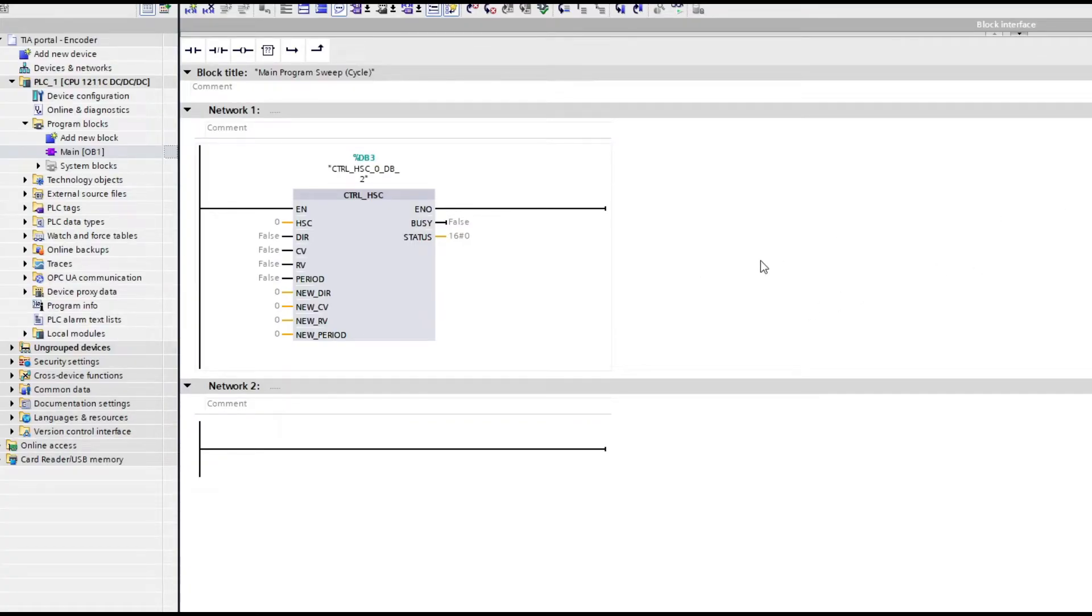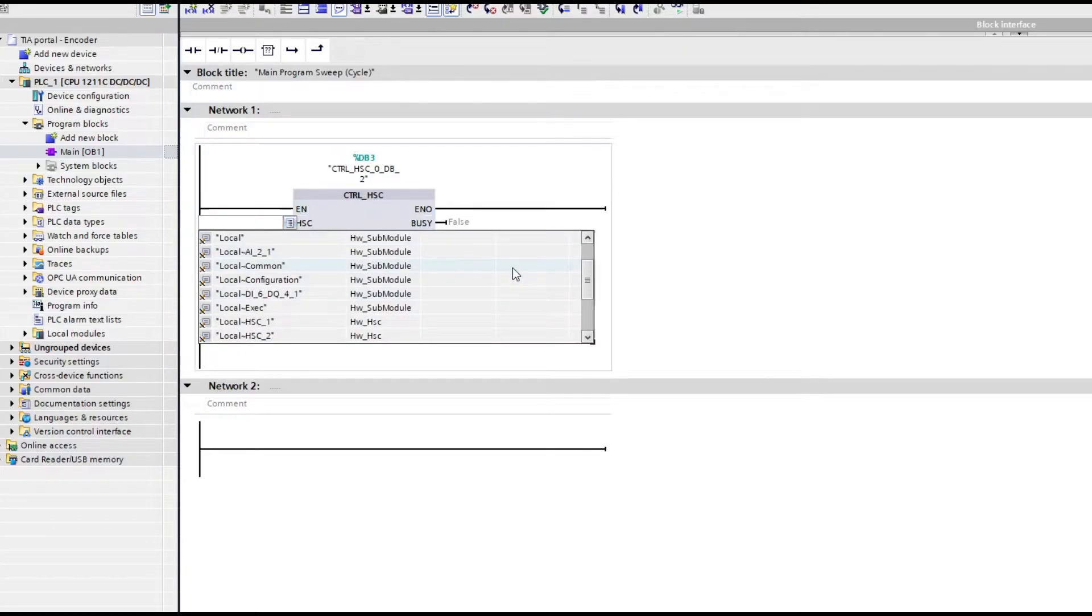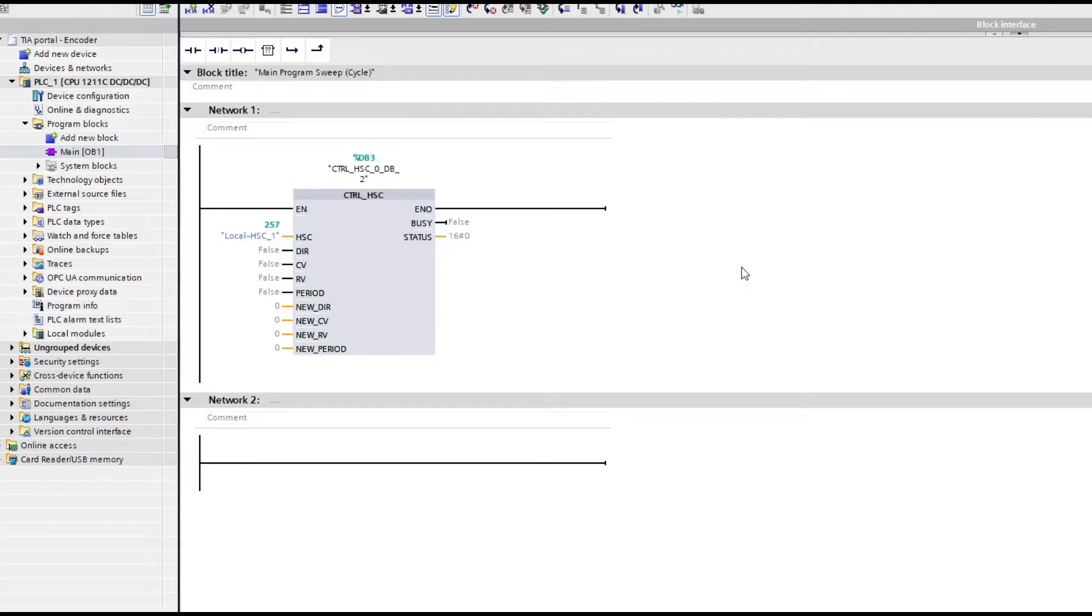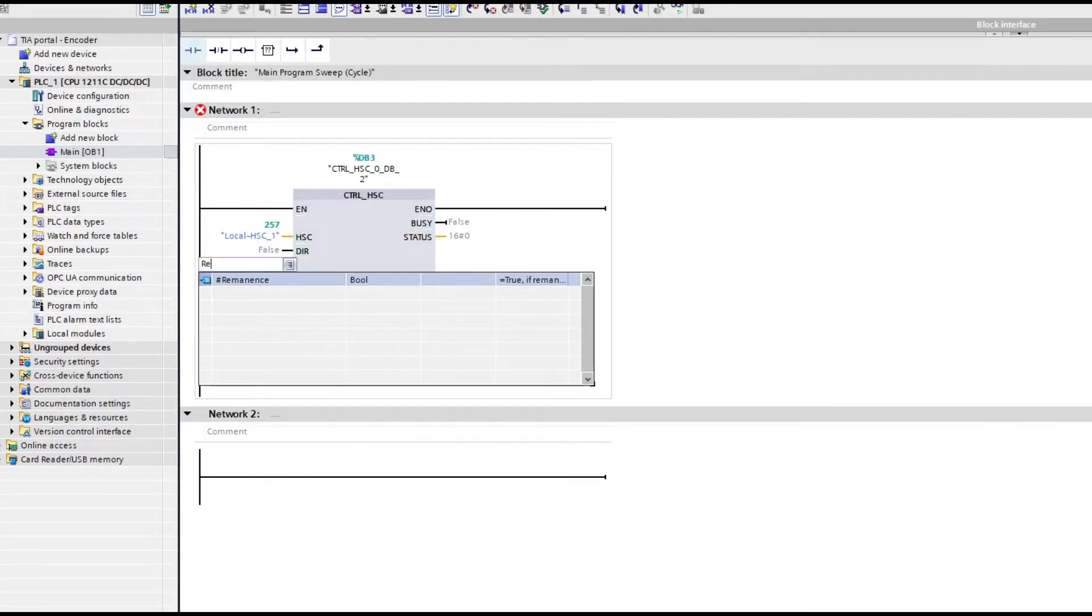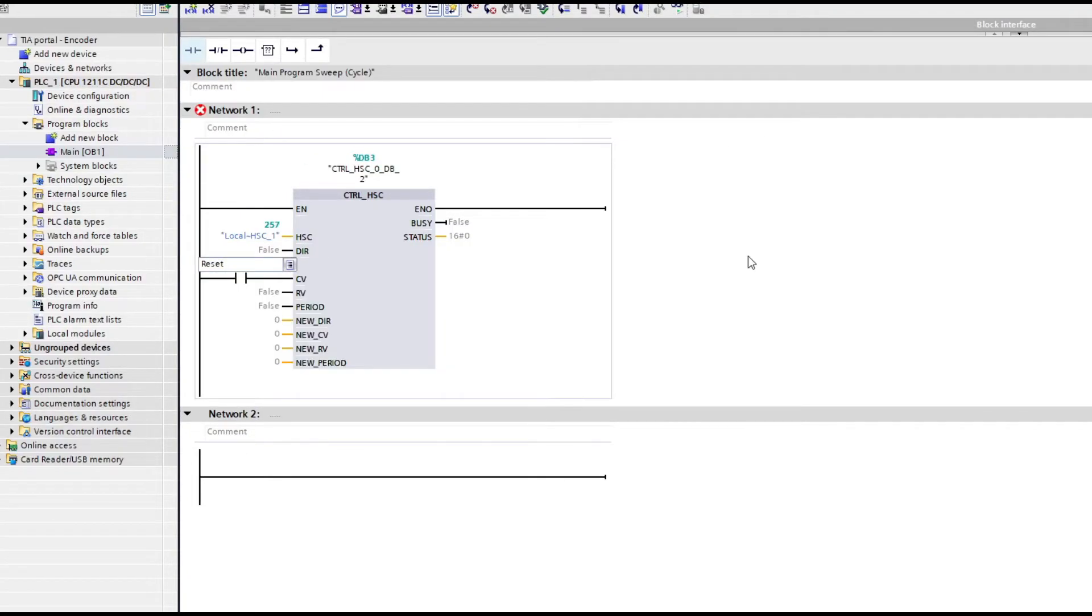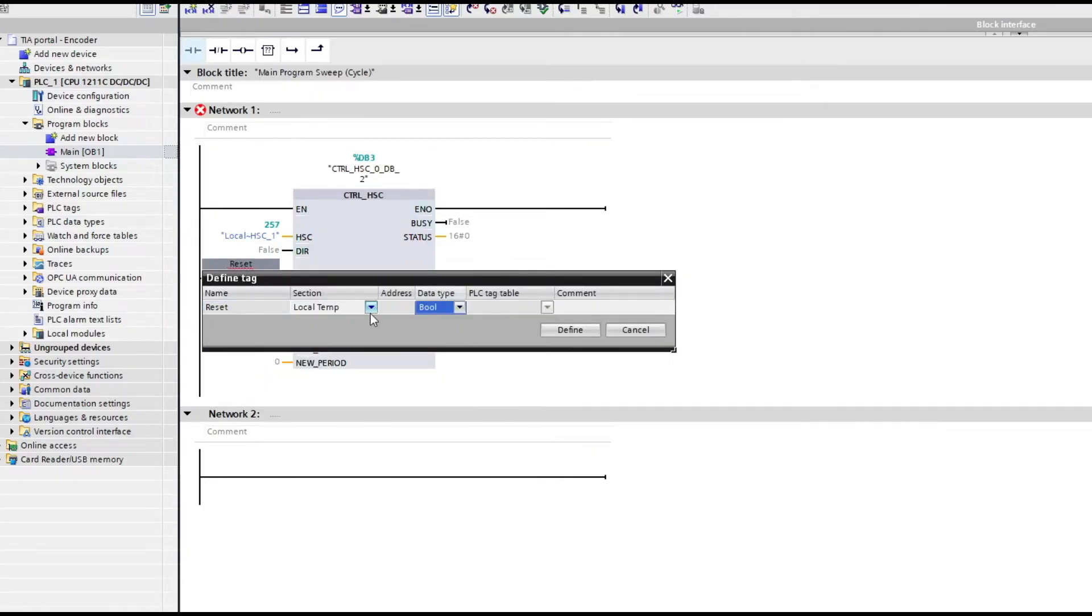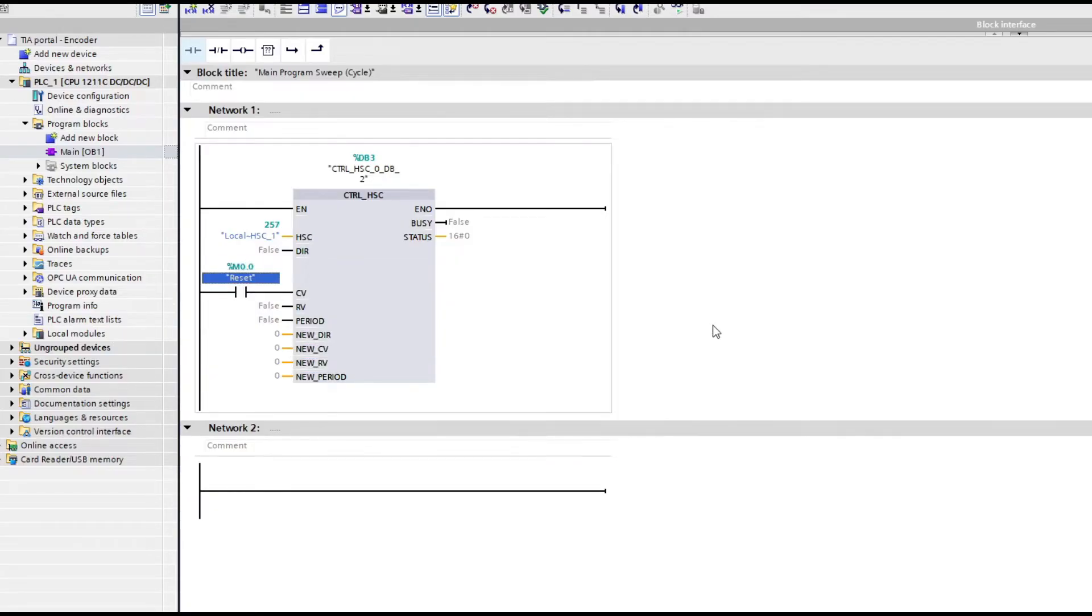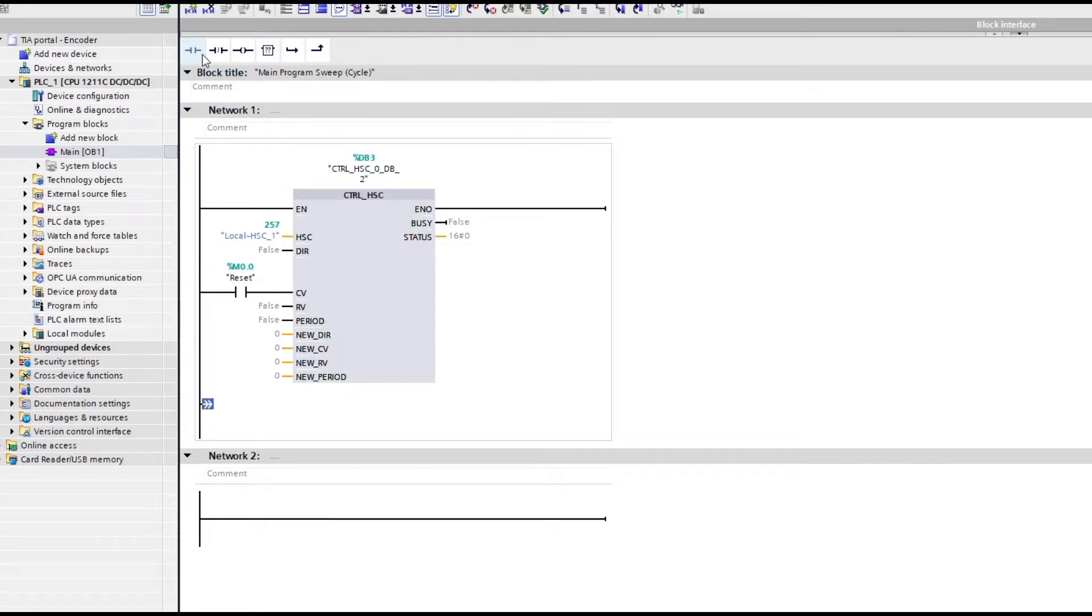On the HSC input we want to open the option list and find the HSC1 that we added earlier. I will keep this really simple and only use the CV input. This input will reset the encoder to zero. I will add a reset memory bit and a comparator function that makes once the encoder counted up to 1800 pulses it will reset itself. The encoder I am using counts 600 pulses per revolution. So after 3 revolutions the encoder will reset itself.